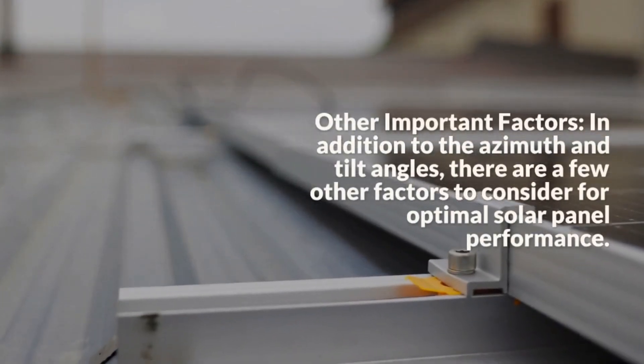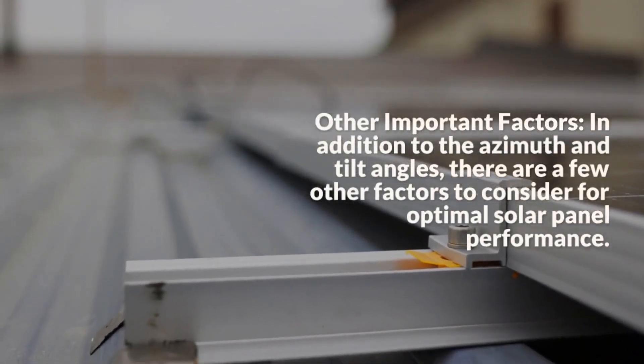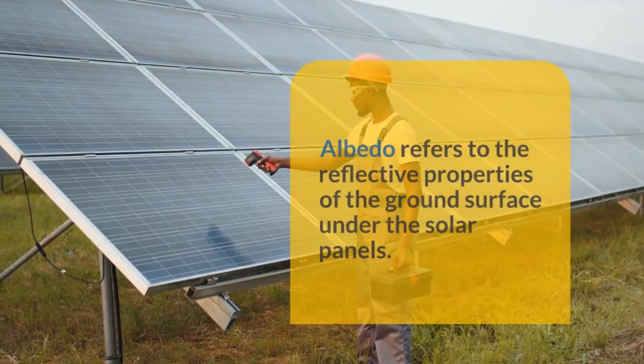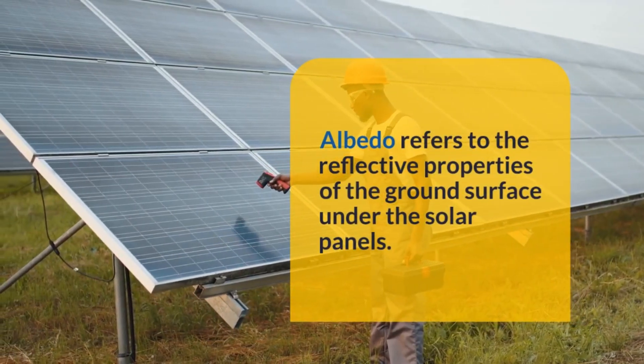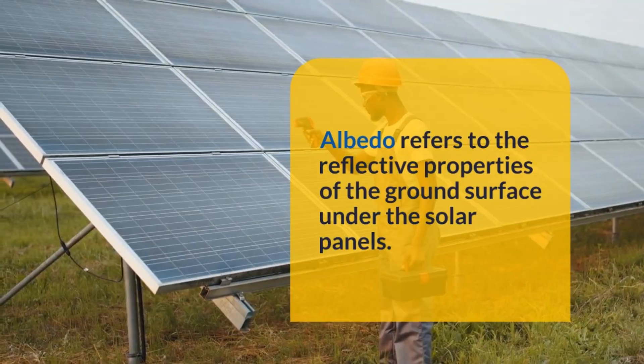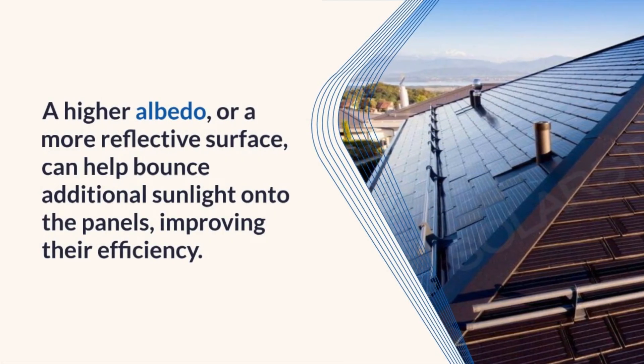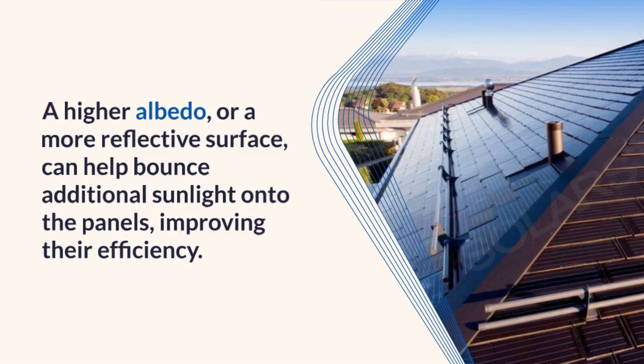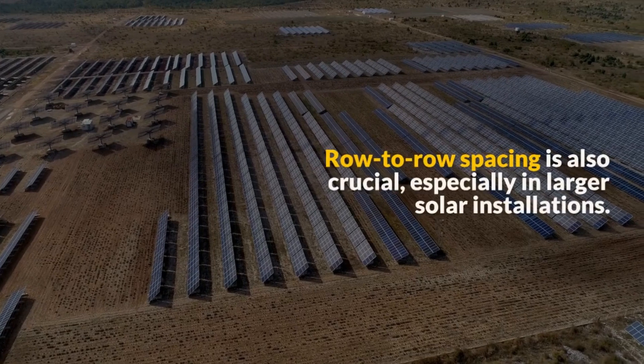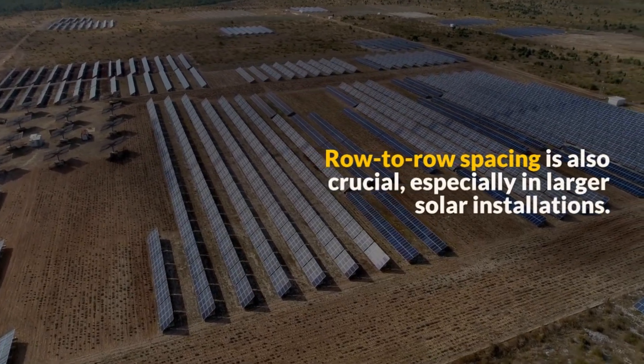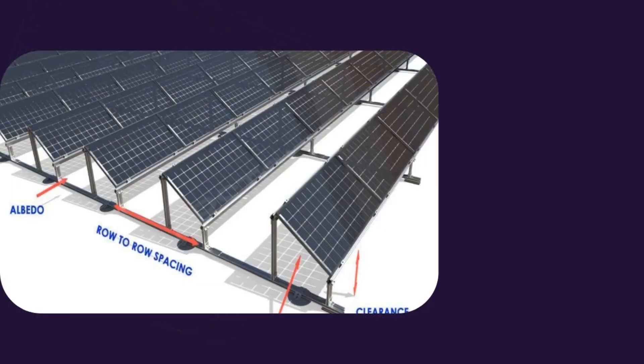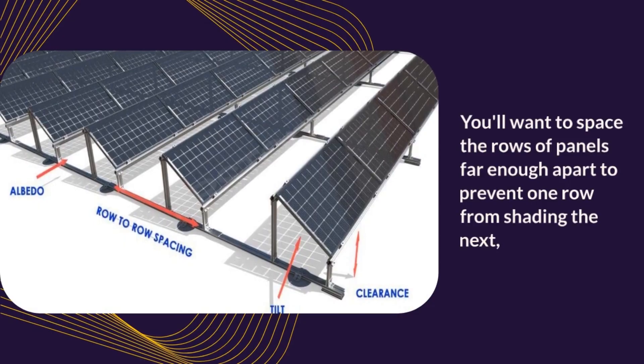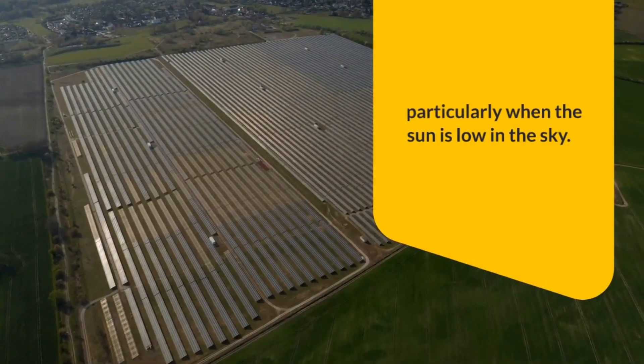Other Important Factors. In addition to the Azimuth and Tilt Angles, there are a few other factors to consider for optimal solar panel performance. Albedo refers to the reflective properties of the ground surface under the solar panels. A higher albedo, or a more reflective surface, can help bounce additional sunlight onto the panels, improving their efficiency. Row-to-row spacing is also crucial, especially in larger solar installations. You'll want to space the rows of panels far enough apart to prevent one row from shading the next, particularly when the sun is low in the sky.